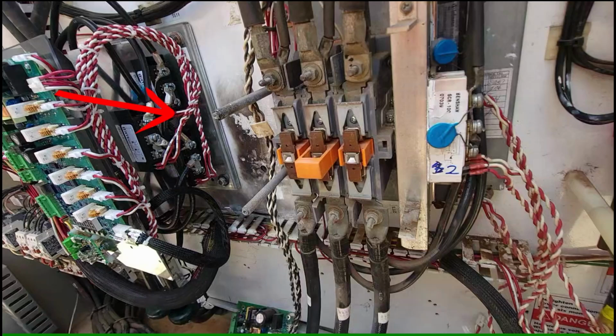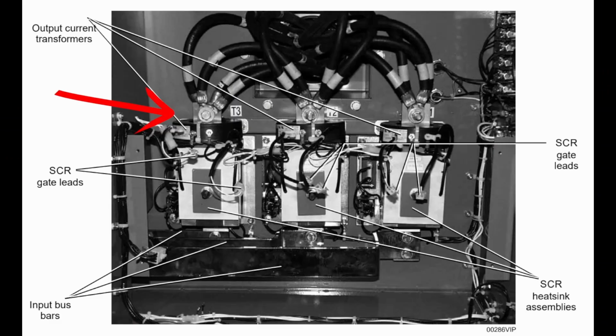Let's see if I can pull up an example of that, where we've got an active control system, or a cooling system, to prevent the starter from overheating. So this would be a type of, there is no bypass contact here. These are SCRs, they're just much bigger, and they have a steady output, but these are mounted to a cooling plate assembly. Now this would be a liquid cooled style of system, where we're flowing a fluid through a heat exchanger, and it's taking the heat away and rejecting it into the condenser water side of the system.